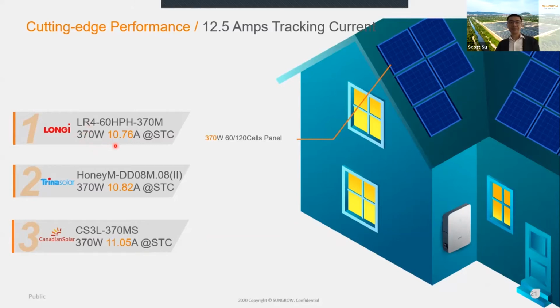The current is 10.76 amps. Trina Solar is 10.82 amps. Canadian Solar is over 11 amps. But for Sungrow, because we have 12.5 amps tracking current, we can very easily handle these panels. But I know some other manufacturers only have 11 amps MPPT current. If so, I believe they cannot be 100% compatible with 370 panels.